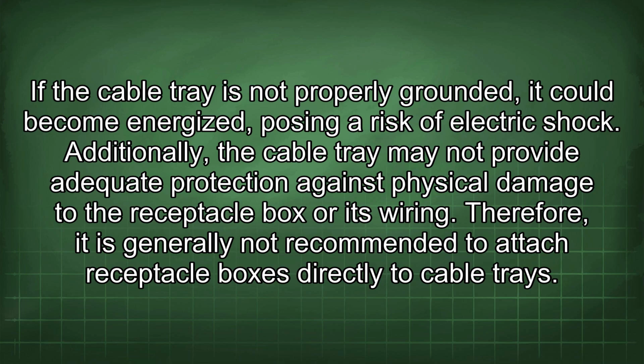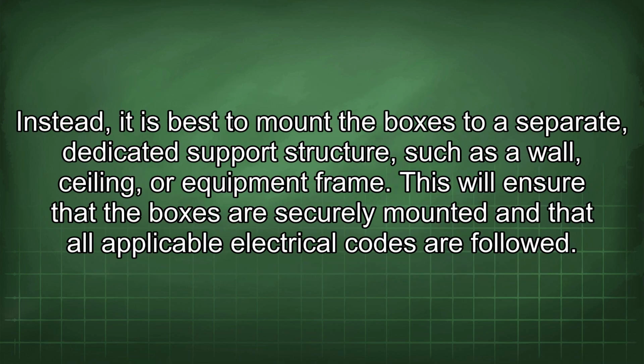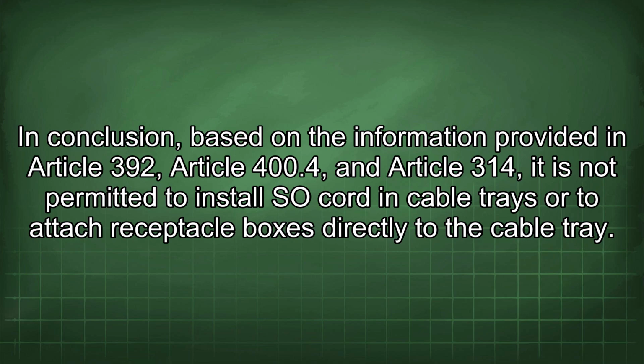Therefore, it is generally not recommended to attach receptacle boxes directly to cable trays. Instead, it is best to mount the boxes to a separate, dedicated support structure such as a wall, ceiling, or equipment frame. This will ensure that the boxes are securely mounted and that all applicable electrical codes are followed. In conclusion, based on the information provided in Article 392, Article 400.4, and Article 314, it is not permitted to install SO cord in cable trays or to attach receptacle boxes directly to the cable tray.